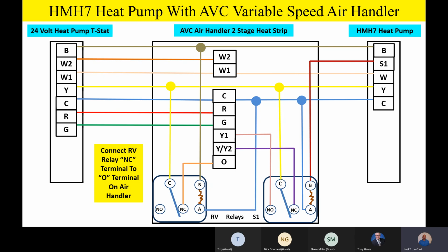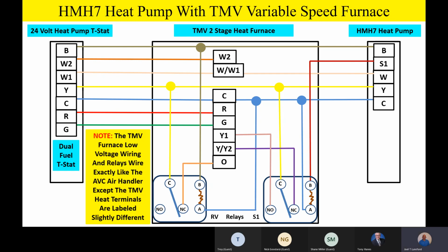Okay, well, let's continue then. Let's say we have a variable speed furnace. I want to stress it wires exactly like a variable speed air handler. So there's nothing different. You have to have two relays. You've got the RV relay, you've got the S1 relay. Everything wires exactly the same. It's just that you'll notice that the terminals on the furnace are labeled slightly different. So you'll see like a W2 and a W/W1 on the furnace. So it's a slightly different labeling, but it wires exactly like the variable speed air handler.